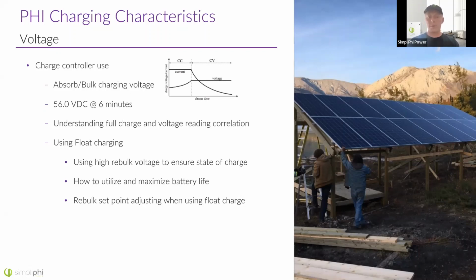So once your batteries are fully charged at 56 volts, that charger is going to turn off. And what's going to happen is you're going to be confused because the voltage is going to immediately drop from 56 down to about 53.3 volts. That's where our batteries sit usually when they're completely full and there's no load on them or no charger on them. So keep in mind, it doesn't mean they're going to sit at 56 volts when they're full.